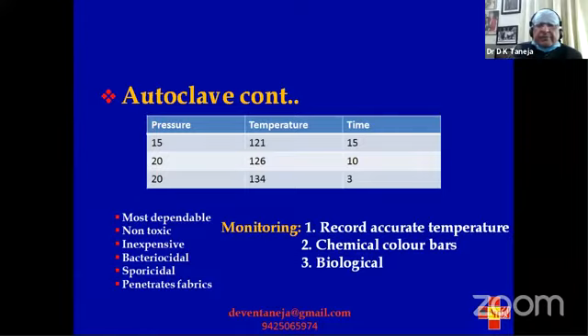And this is a very commonly asked question: how much pressure, how much time you will give it. Now, if your pressure is 15, the temperature will be 121 degrees, and you take 15 minutes. If your pressure goes higher, to 20, the temperature will go to 126, and your time of sterilization will come down by 5 minutes, to 10 minutes. If the pressure is again 20 and you raise the temperature to 134, within 3 minutes your spores can get killed in an autoclave, and this is called flash autoclaving. Sometimes an important instrument has fallen down, you tell your OT nurse, I want this instrument immediately. Within 3 minutes, they can autoclave it and give it back to you.